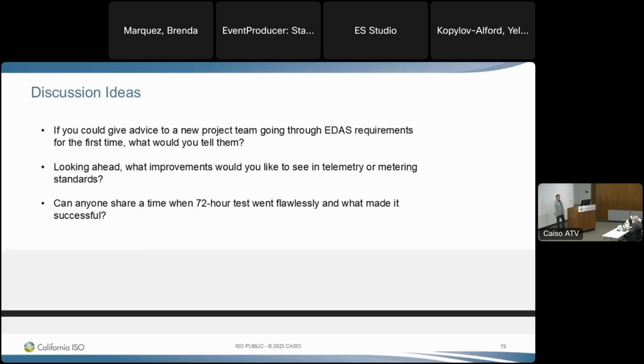Further, multi-fuel resources like solar and BESS have a number of conditions that are near net zero - BESS idle, nighttime, very small loads. The 0.3% accuracy of a CT cannot measure light loads like that. You'd at least need a special range, extended range, 0.15% accuracy to cover something that's only going to have a couple of amps output. Otherwise, these CTs are acting outside of what they're designed to do to try to produce a revenue grade result.